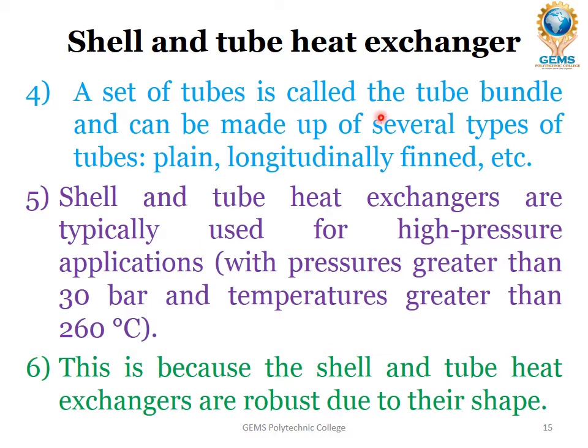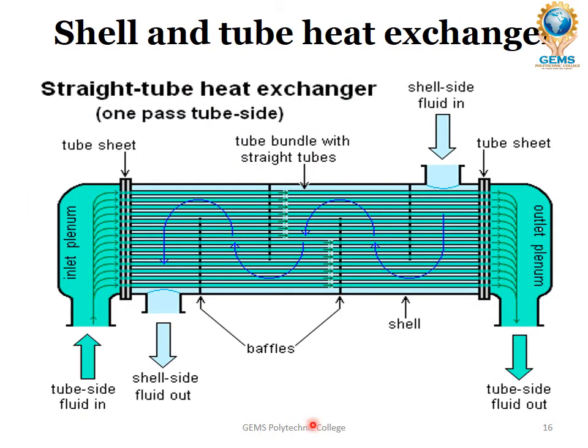A set of tubes is called the tube bundle and can be made up of several types of tubes: plain, longitudinally finned, etc. Shell and tube heat exchangers are typically used for high pressure applications, with pressure greater than 30 bar and temperatures greater than 260 degrees Celsius. This is because shell and tube heat exchangers are robust. So this is a diagram illustrating the shell and tube heat exchanger.